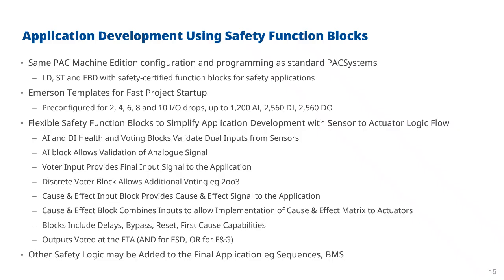So those flexible safety function blocks do considerably simplify the application development, and they give you a lot of extra capability, and they are safety approved. So that obviates the need to do a lot of testing in the application itself, because our safety function blocks provide that certified capability without you having to write the extra logic. Other safety logic may be added to the final application. So for example, you may have some sort of sequence, particularly for BMS, you may have other logic, but generally a safety system will normally be self-contained. So it would be expected that you'd rarely find additional logic outside of safety logic within the safety controller itself. The idea is a safety controller performs safety functions. You would have a separate process controller to perform process control, and maybe another controller as well to perform process shutdown. But typically process shutdown and process control are combined, but you'd have a separate safety controller.